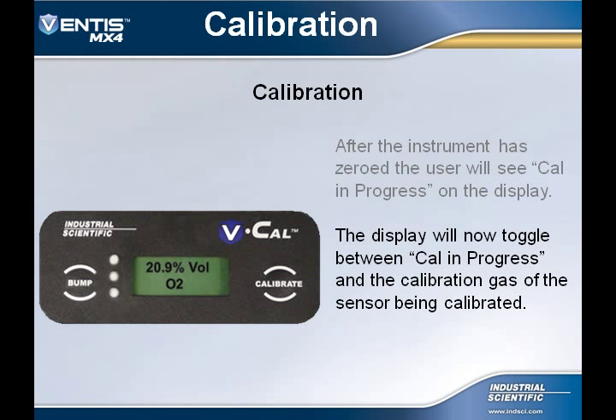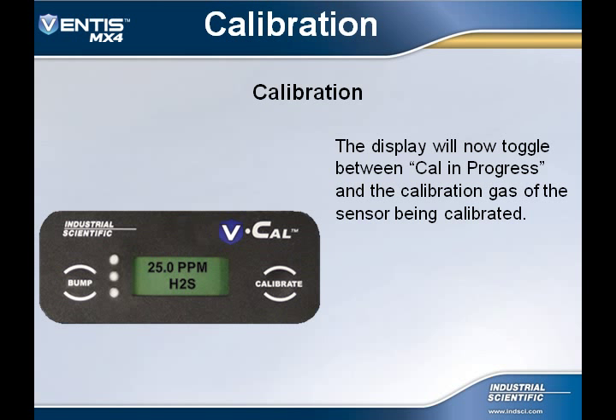The display will then toggle between cal in progress and the sensor type being calibrated, as well as its calibration gas concentration. The display will then toggle between cal in progress and the next sensor type being calibrated. The display will then toggle between cal in progress and the next sensor type being calibrated. And lastly, the display will then toggle between cal in progress and the last sensor type being calibrated.